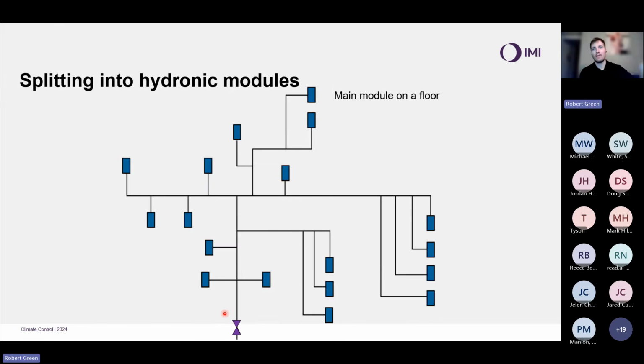So we're now going to look at the main module on the floor. We get to this point here. We can go left, right, or straight on. The main flow is going straight on. So we place a balancing valve on the left and the right. We have the same scenario here. The main flow is still going straight up. So we place a manual balancing valve on this unit on the left.